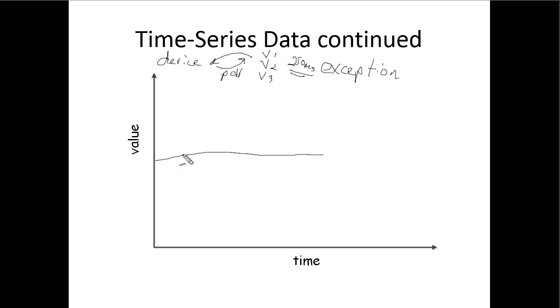So I say maybe as the values come in, okay, they're coming in here. And I say, okay, so this reading is virtually the same as this reading, virtually the same as this reading, virtually the same as this reading. I don't need to save those. I can save this one right here, and then maybe every 8 hours or so, I'll save one just so that I know I'm putting something in my database. I know I took a reading.